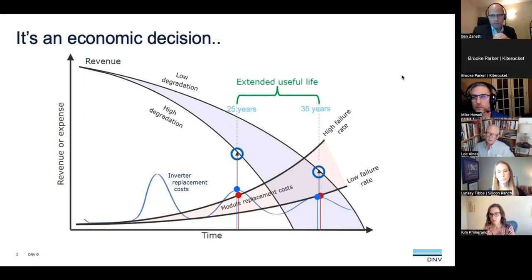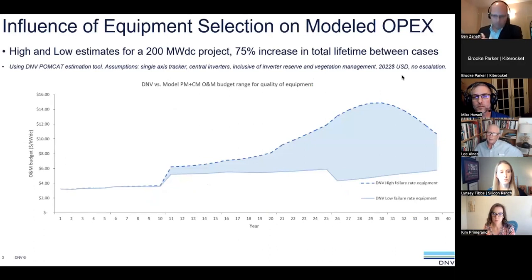In your next slide, you modeled a 200 megawatt plant. Can you speculate how this would change at 20 megawatts, 2 megawatts, or 200 kW? I'm sure it's quite different, but what's the impact across the broad range of projects we're dealing with? Obviously it's easier to model a larger site because statistics kick in when you have 150 inverters versus 5 or 6. It's much easier to rely on the statistics, so the model does become less accurate below 50 to 20 megawatts, somewhere in that range.